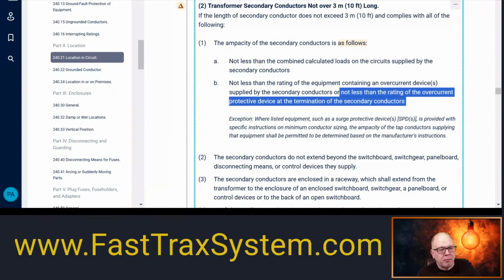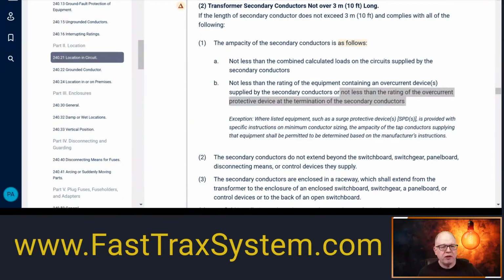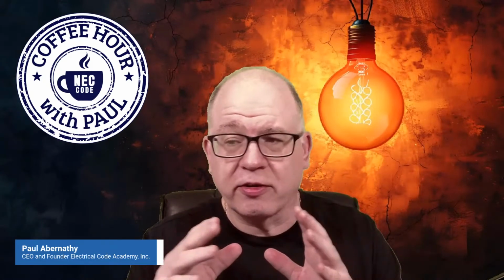That's probably what we're going to see the most in our applications: we come out of a panel, and we're doing it because we need a different voltage. So maybe we have 480 volt in the building, and we need 120/208. We're coming out, hitting a transformer pretty close, under this 10-foot rule, and then on the load side of it we're hitting a panel, so we're changing the voltage. Maybe we're doing lighting, where the 480 was generally for motor applications, and we need a transformer to serve lighting loads, things like that. So that's what you might run into.